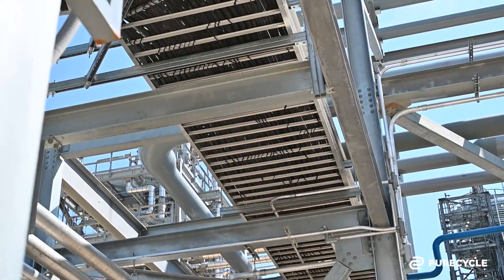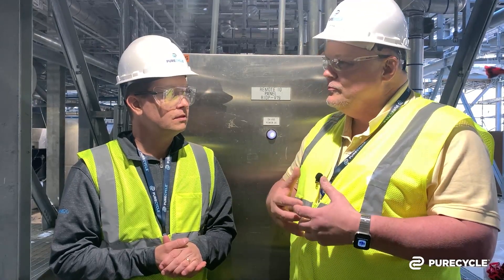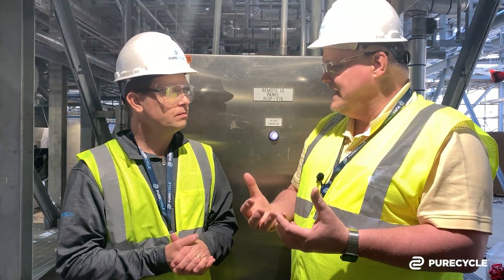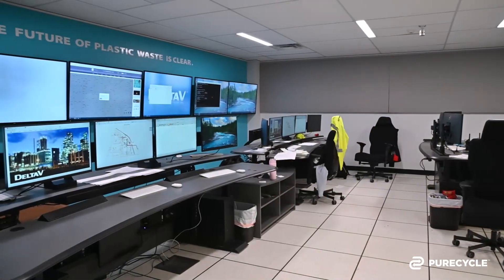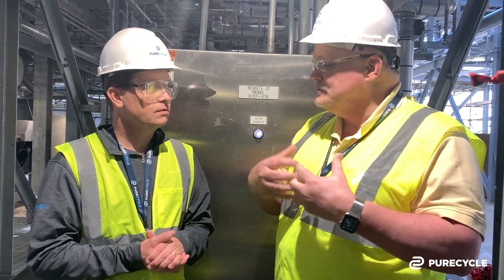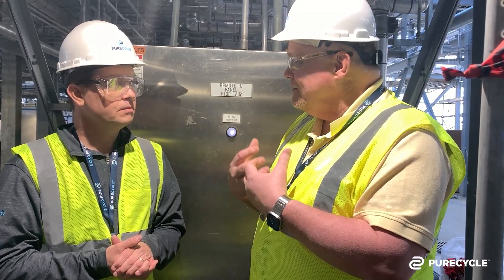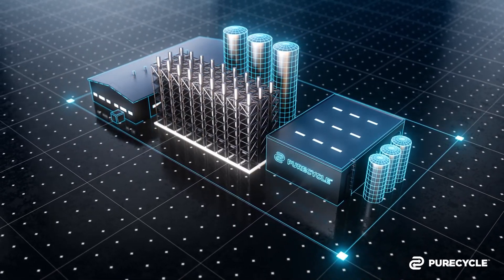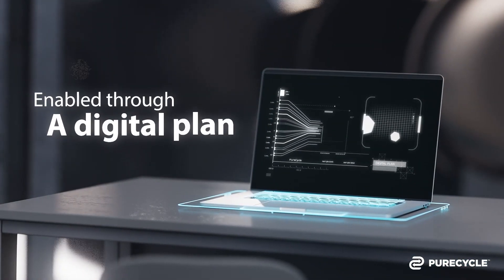You would have it anyway, but the way we arrange it and the way we connect it creates this Born Digital methodology where we don't have to go through a transformation later. Built into that is a tool called Asset Management System, or AMS, that we can use from the control room to automatically check out every device in the plant. It's the first process I've ever been involved in where the checkout team is ahead of the construction team — they don't have this huge lag at the end. They can see immediately through the digital network: the beauty of Born Digital.